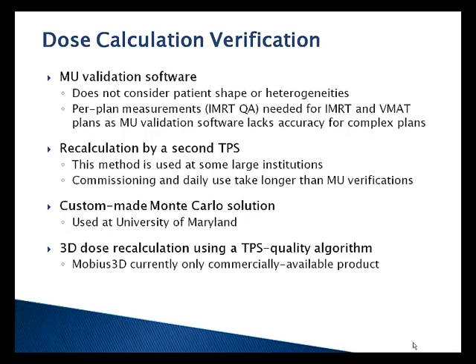But we end up doing IMRT QA for any complex plans to make sure we're delivering the right dose to the patient. We recalculate. Some places can recalculate by second calculation system, second TPS. It's a little bit more time consuming. Some places, like University of Maryland, have a Monte Carlo secondary calculation system. It's a pretty neat idea. And then what we developed, Mobius 3D, is actually basically a planning system that doesn't plan and just recalculates dose using the same quality algorithm. So a lot of options available.